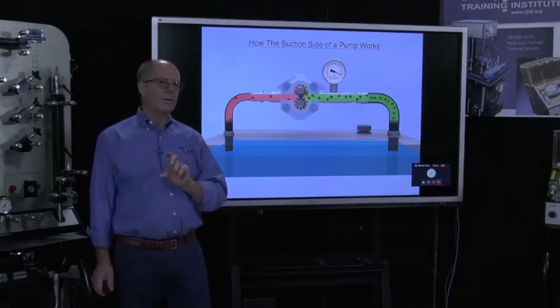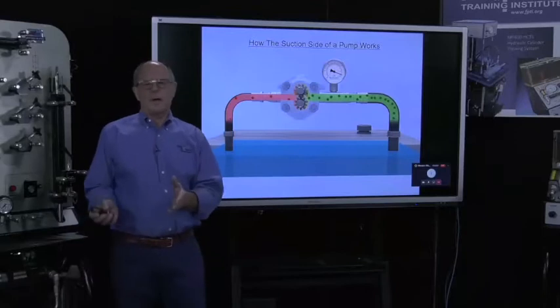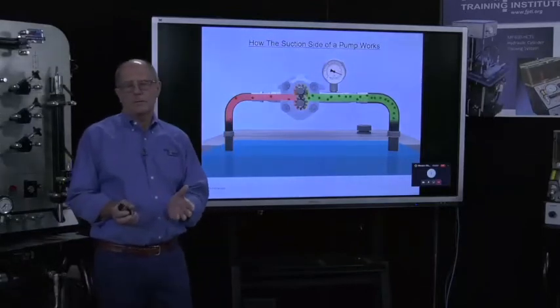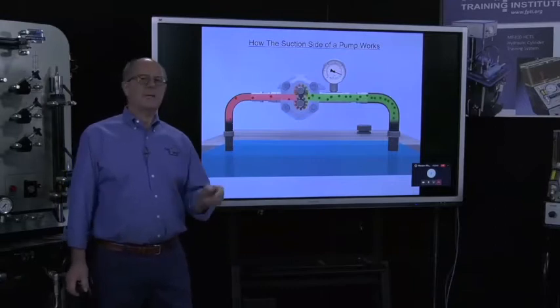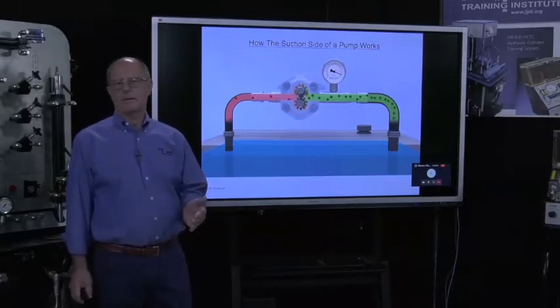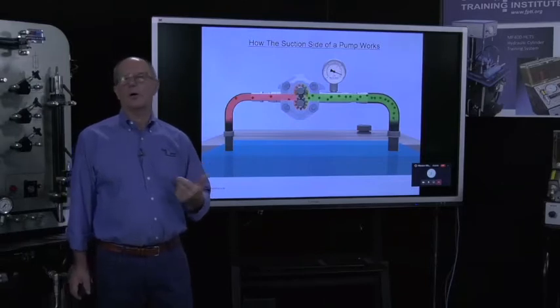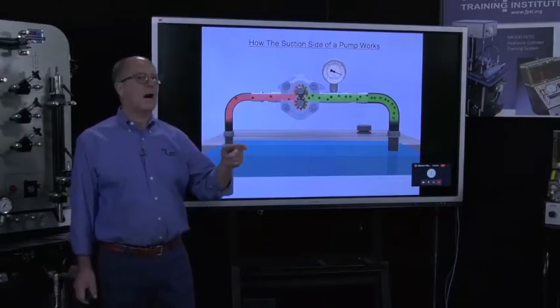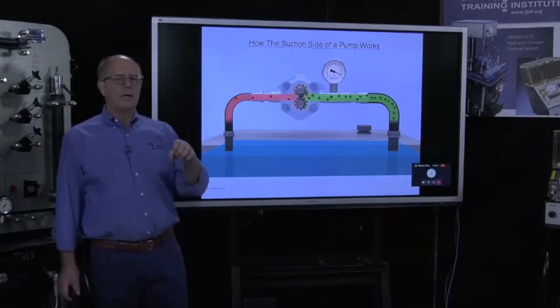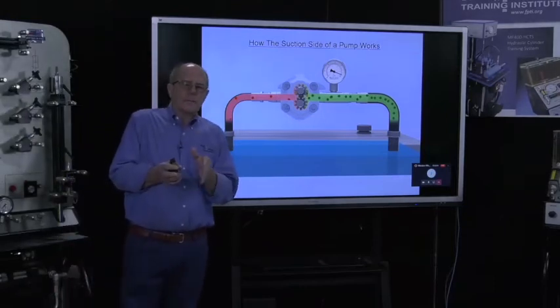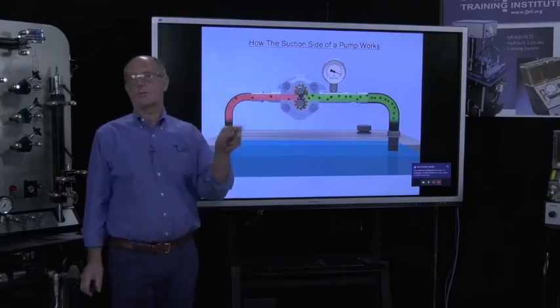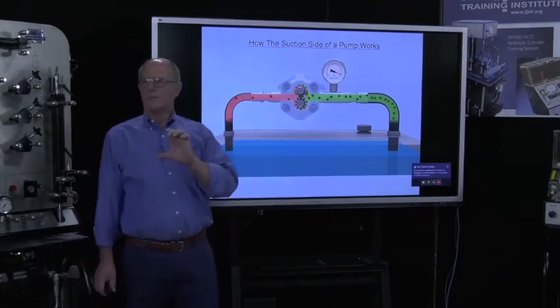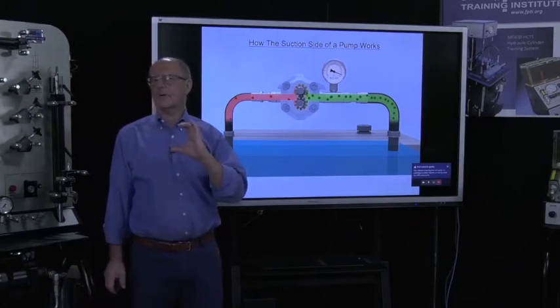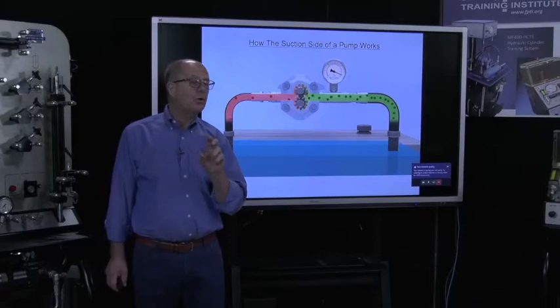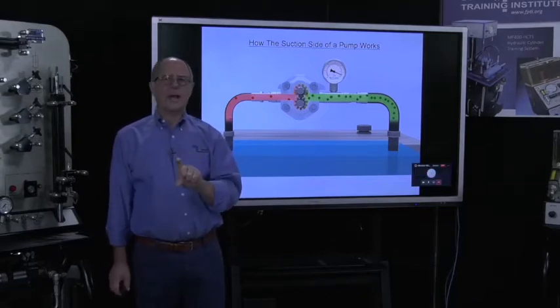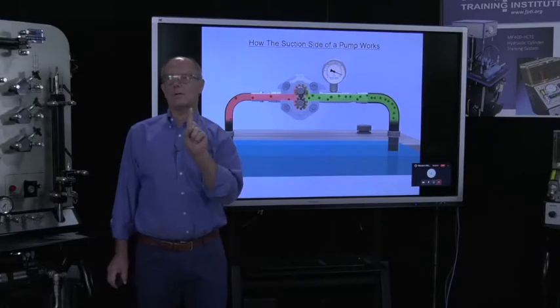Now, when I say well within, you have to realize that if you go out to the assembly line on a prototype machine and the weather's reasonable, let's say ambient temperature is 80 degrees, and you're at 7, you have to realize if this machine is going to work in a cold environment, it's going to go way over the top when the oil is cold. So it must be well within that number. The engineer does two things, or is supposed to do two things. One, establish that I'm well within the pump manufacturer's recommendation. And two, when I do that, I will establish the pump's inlet restriction point of reference.